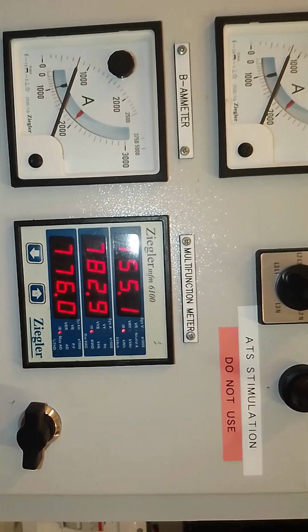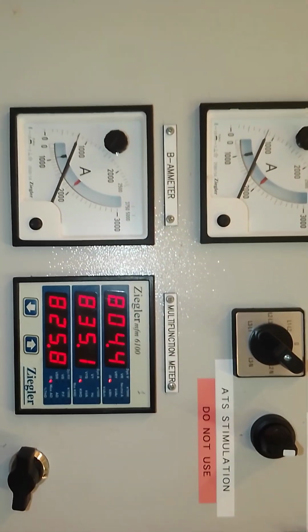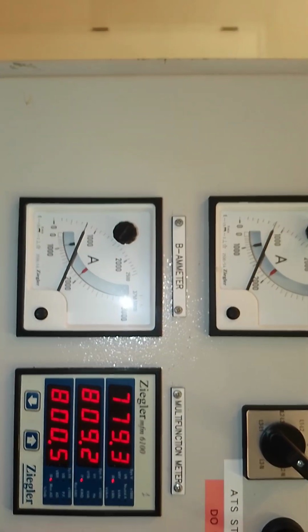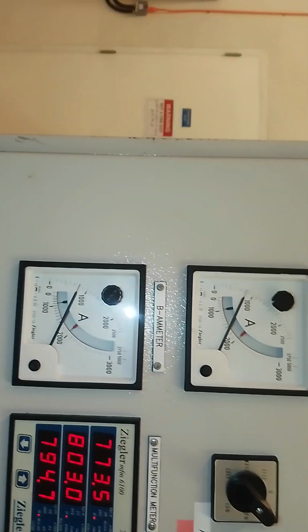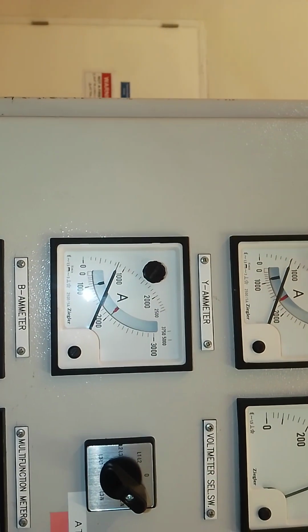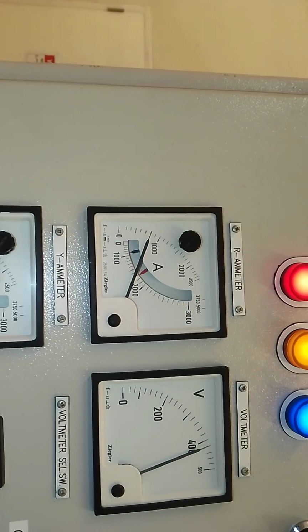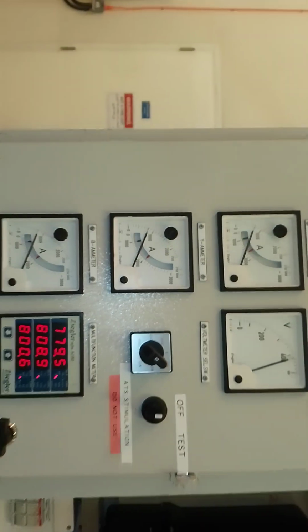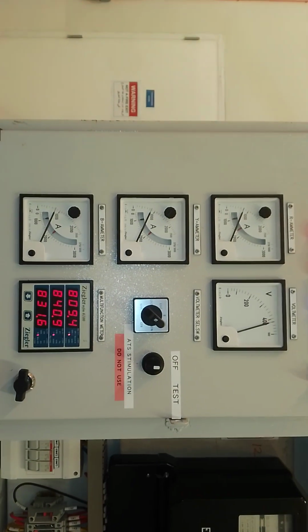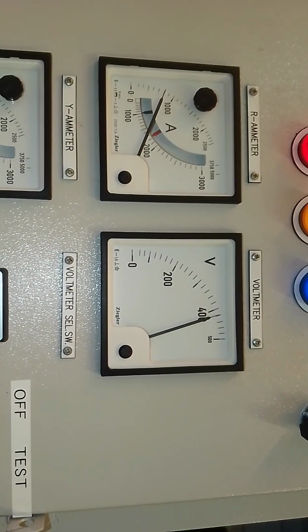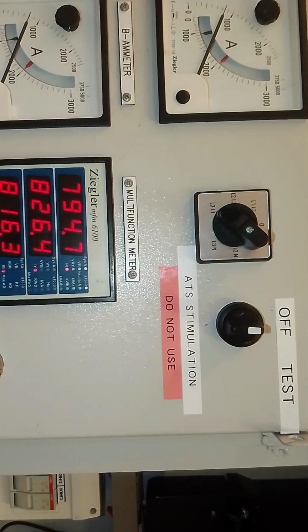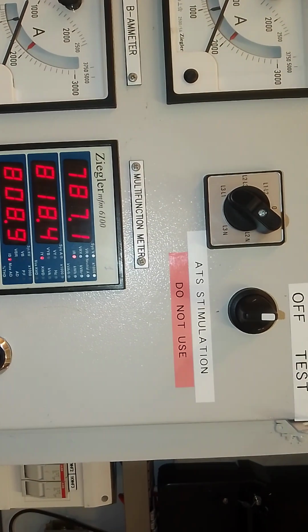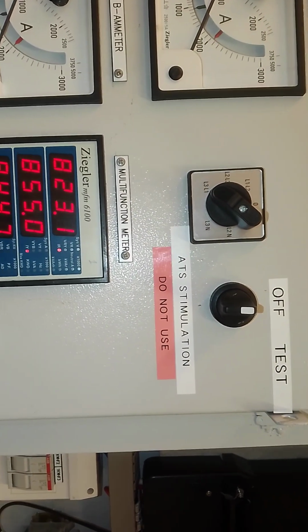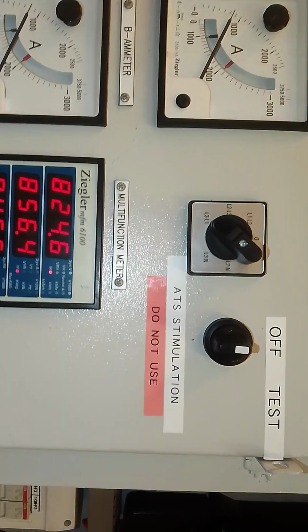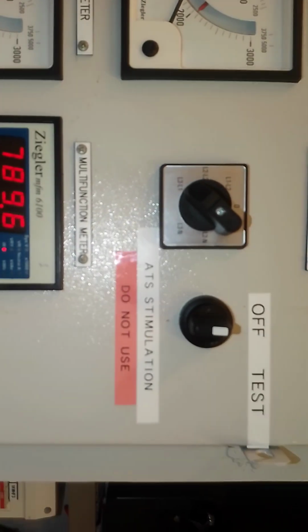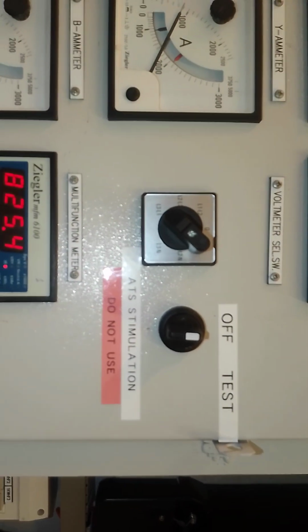This is our multifunction or digital meter. This is our ammeter, analog ammeter. That is red, yellow and blue, and also voltmeter, analog. This one is ATS stimulation switch for testing when you are doing tests, generator tests, because this one is connected also with generator, which is automated.